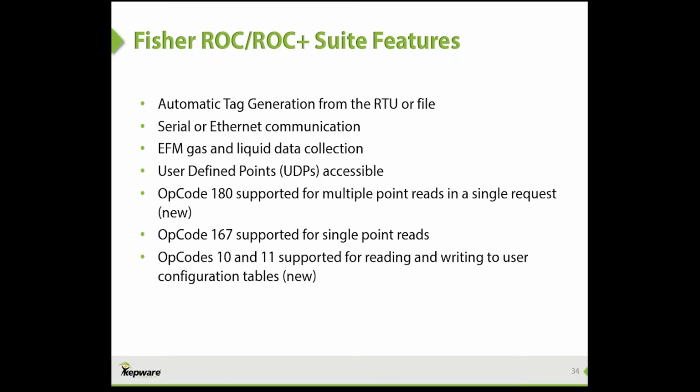So what are the new suite features now that we've added in? Previous existing features and new features that we've added in. We did previously support automatic tag generation from the RTU or file, and that's for rapid deployment. We have the serial and Ethernet communication, support for EFM data collection, access to user-defined points or UDPs for enabling data used in user programs, support for opcode 180 for multiple point reads, opcode 167 for single point reads, and opcodes 10 and 11 for reading and writing to user configurable tables.